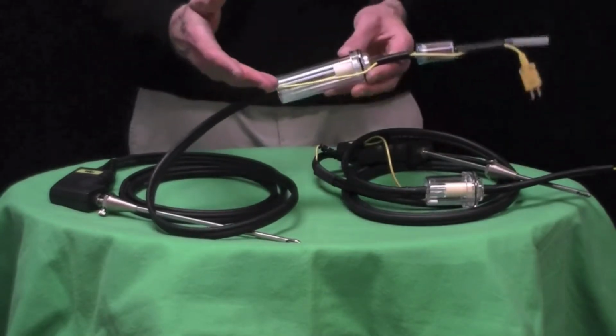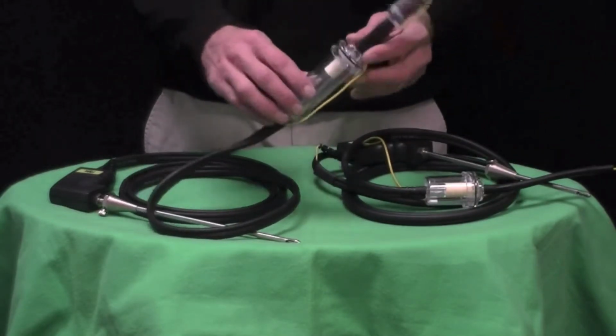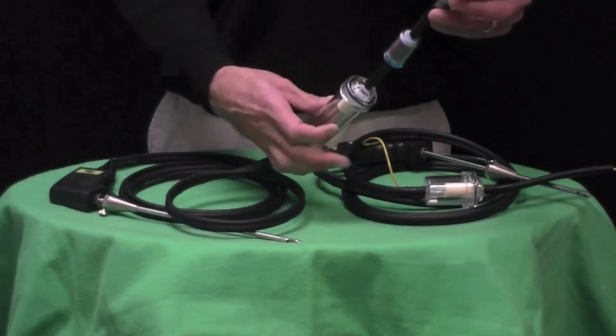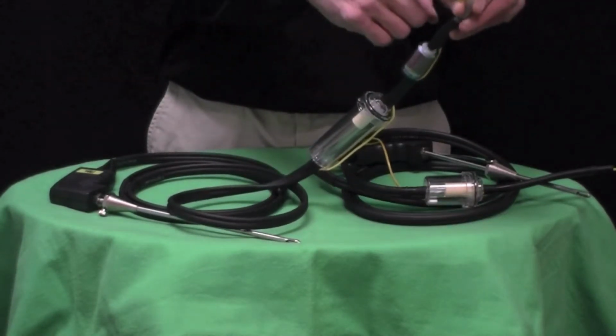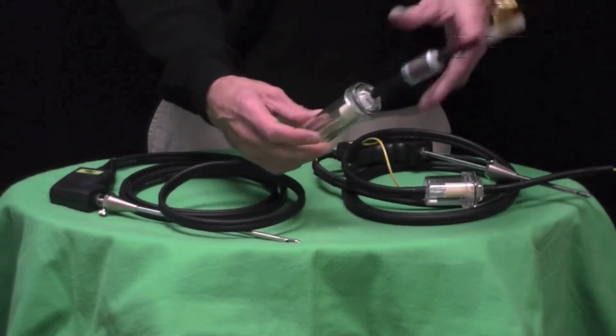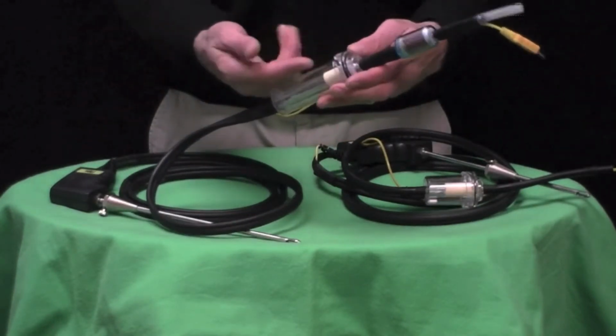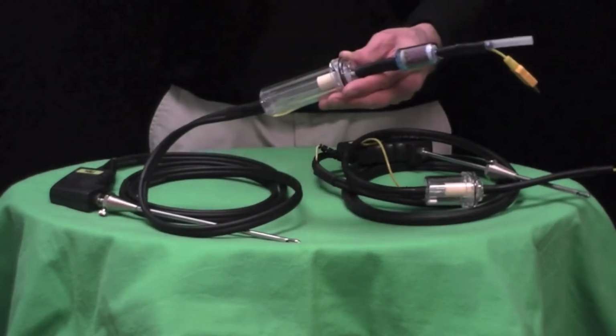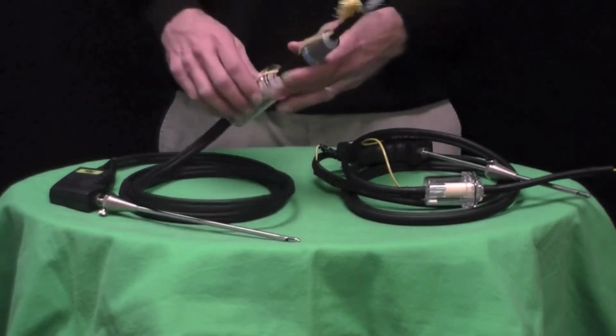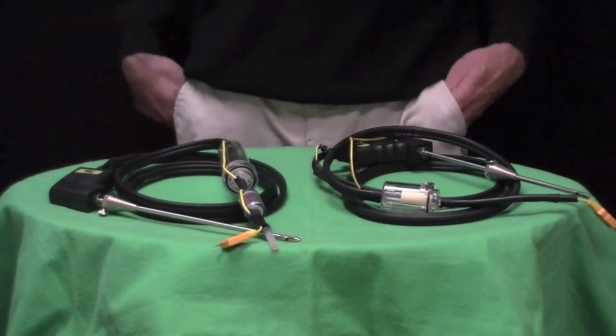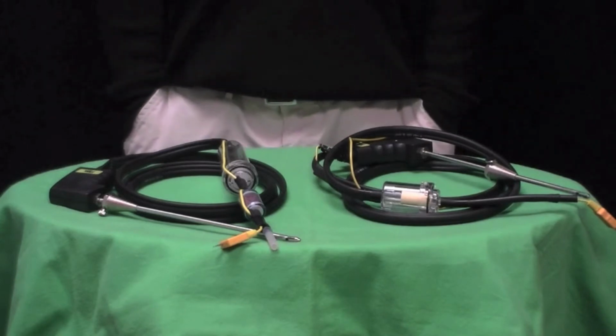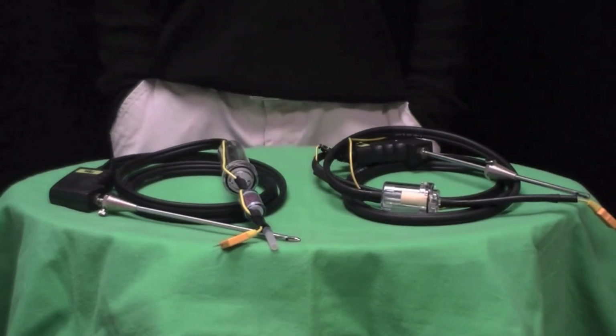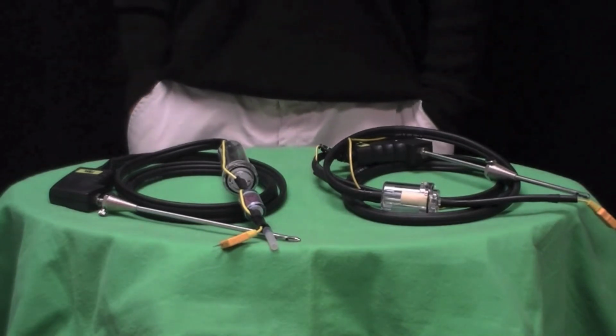The only important thing to remember is when replacing the water trap, the paper filter should point to the top, toward the yellow cord, the K-type thermocouple. That way, when water rushes through here, it's correctly oriented into the analyzer. So that's just a little tip on how to make sure your A773 oil filter is correctly installed in your 700 series combustion analyzer.